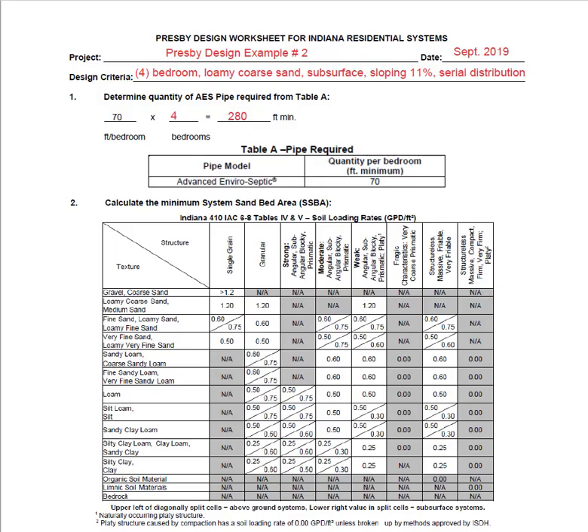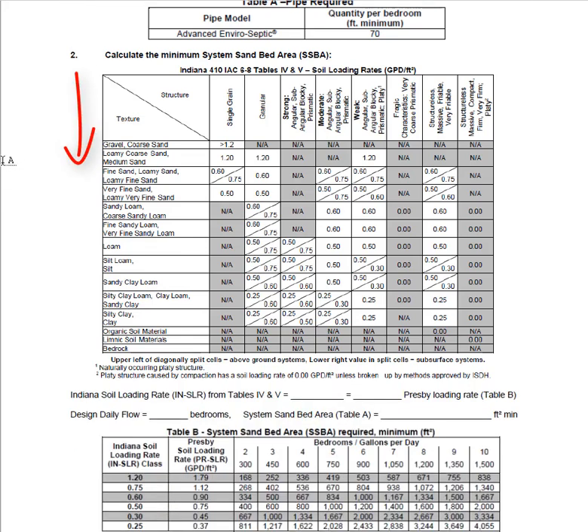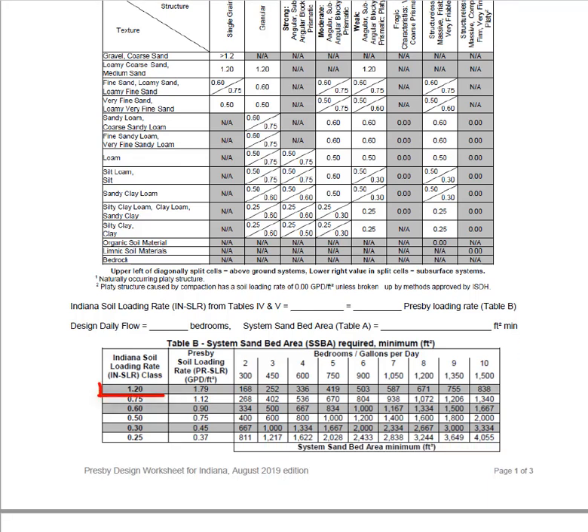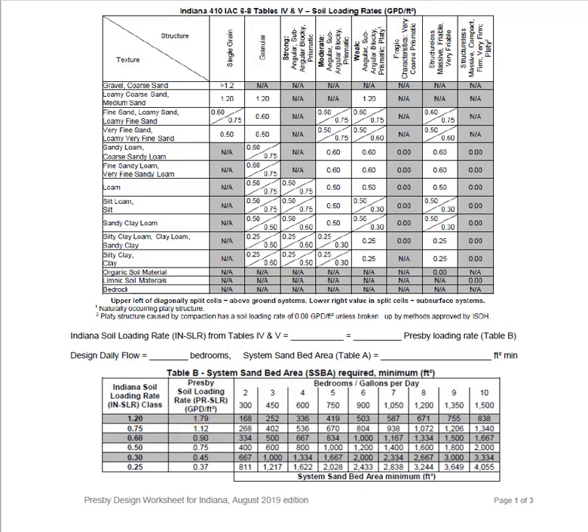In step number two we're going to calculate the minimum system sand bed area. You will see the table for Indiana soil loading rates below. We need to determine this loading rate based upon the on-site soils — in our case, loamy coarse sand. Look down the texture column of the table until you find loamy coarse sand. The Indiana soil loading rate is 1.2 gallons per day per square foot regardless of structure. Now that we have the Indiana loading rate, we can find the corresponding Presby loading rate in table B. Once we find 1.2 gallons per day per square foot, we move directly to the right and find the Presby loading rate, which in this case is 1.79 gallons per day per square foot. We will record these values on our sheet.